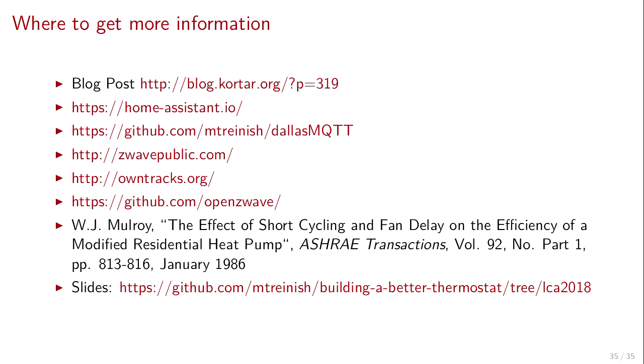But here's a bunch of information, including the blog post, a link to the slides, and a very interesting paper for people who want to learn about heat pump and air conditioner cycle times and efficiency curves, because I had to research this to figure out how to best optimize it. The only research was actually done in the 80s, because back then, solid state electronics were getting cheap enough that people were selling short cycle modules for their air conditioners and heat pumps, saying it's on less, it's going to save you money. And these guys wrote a paper saying that's bullshit.